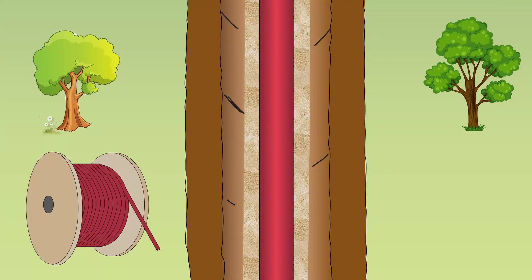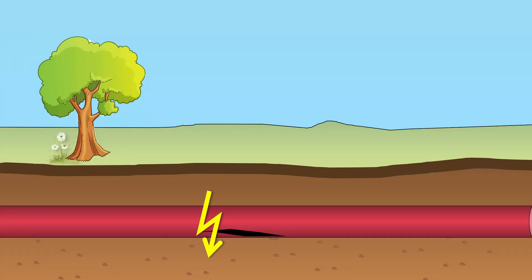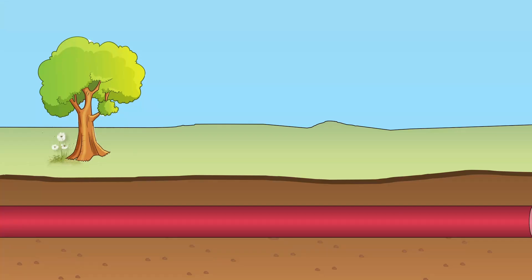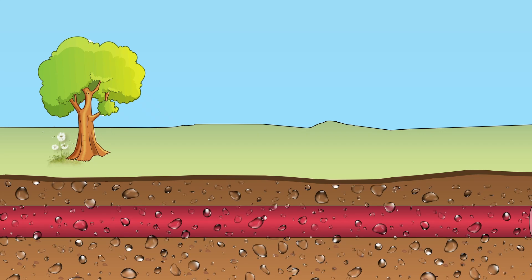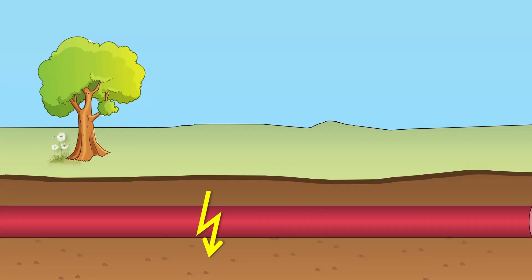The laying of underground cables should be done very carefully. If you are careless during the pulling of the cable, it may damage the cable, which results in fault occurrence. This is not the only reason for the fault. There are many other reasons such as manufacturing defects, aging, and if somehow moisture enters the cable, it will also cause faults. Since the underground cables are buried, if a fault occurs, it is invisible to our naked eye.